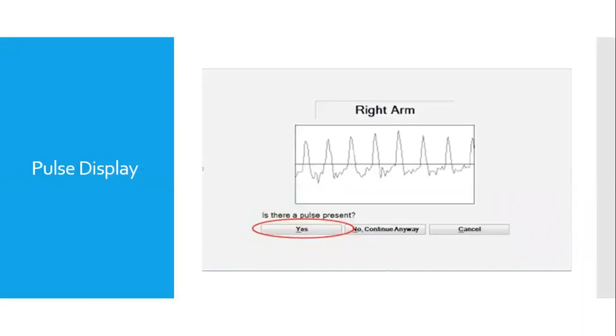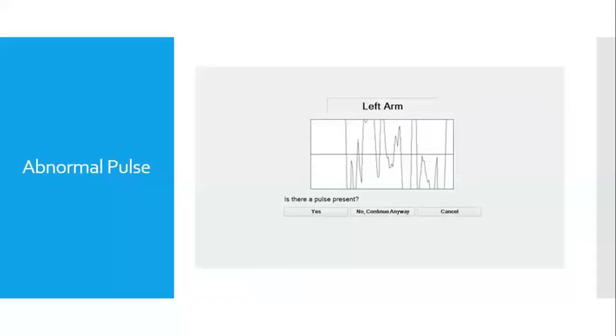When the PADnet test is started, it will first ask you if the PPG probe is displaying a pulse. If the PPG is showing you a regular, even pulse with peaks and troughs, you are in good shape. However, if it shows you an uneven pulse or noise, you may need to adjust your probe and try again.